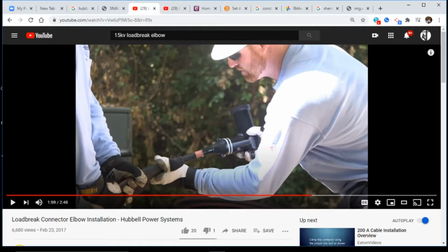Put grease on the wire, then they put the elbows on. Well, petroleum and rubber don't mix, and those elbows quickly failed. You've got to use the silicone grease in the supplied package, and don't put it on over generously. A thin film. You put too much on, it's going to create an obstruction to pushing the elbow on. It's going to be a lot more difficult to push it on.